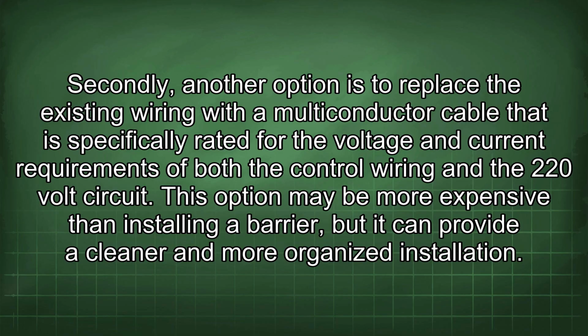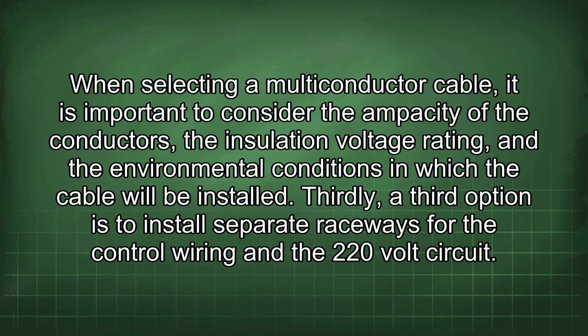Secondly, another option is to replace the existing wiring with a multi-conductor cable that is specifically rated for the voltage and current requirements of both the control wiring and the 220-volt circuit. This option may be more expensive than installing a barrier, but it can provide a cleaner and more organized installation. When selecting a multi-conductor cable, it is important to consider the ampacity of the conductors, the insulation voltage rating, and the environmental conditions in which the cable will be installed.